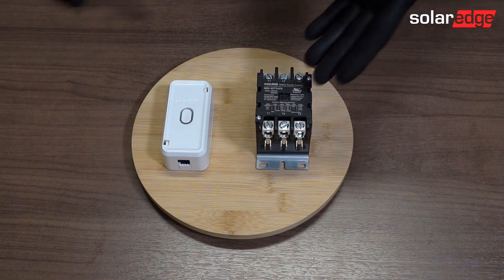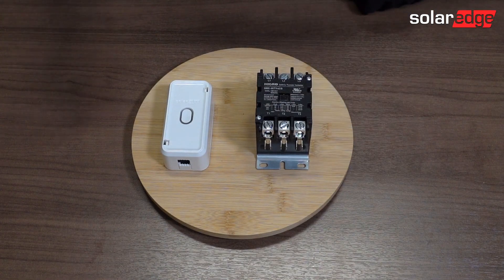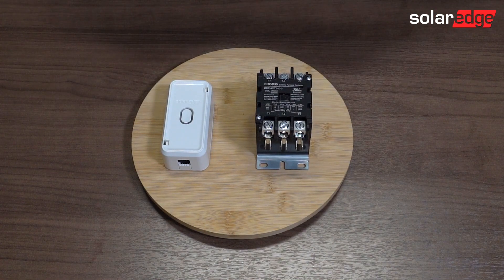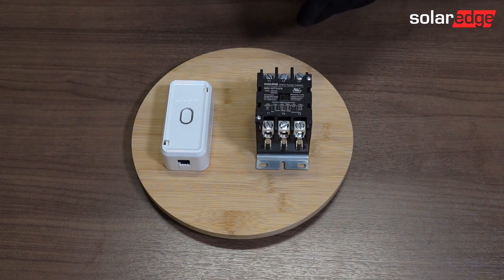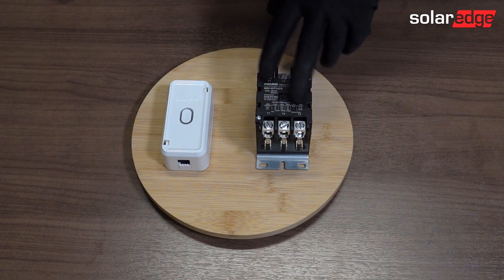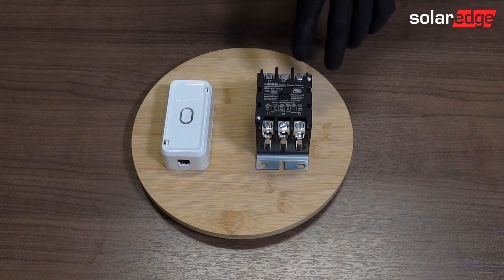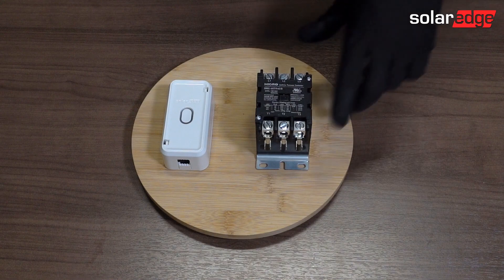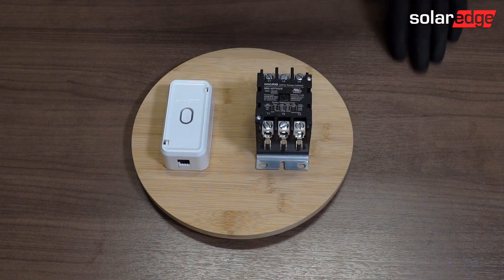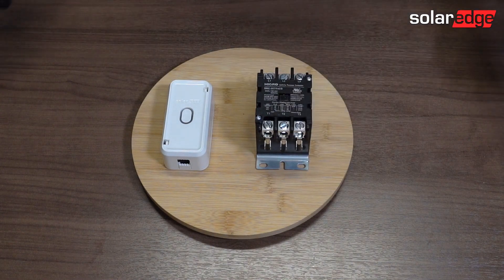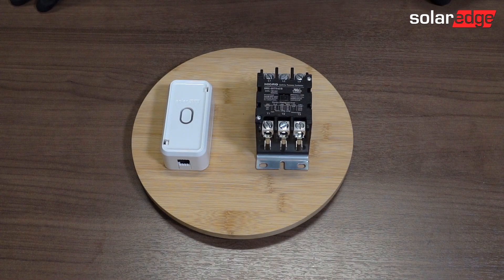Now, the reason we're using a three-pole contactor is because when you get above 60 amps, the two-pole contactors get kind of expensive. And this is a more cost effective solution. So you can use a three-pole contactor in a two-pole application to just abandon this last pole. And that's exactly what we are going to do.